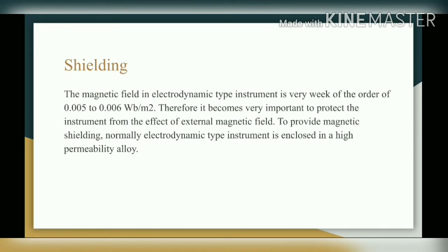Next is shielding. The magnetic field in the electrodynamic type instrument is very weak, of the order of 0.005 to 0.006 Weber per meter square. Therefore, it becomes very important to protect the instrument from the effect of external magnetic field. To provide magnetic shielding, the electrodynamic type instrument is enclosed in a high permeability alloy, which avoids the effect of external stray magnetic field and reduces errors.